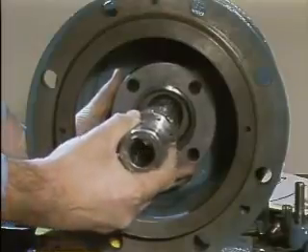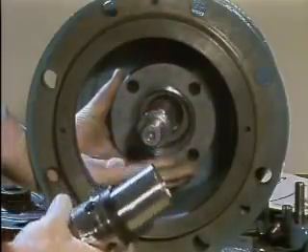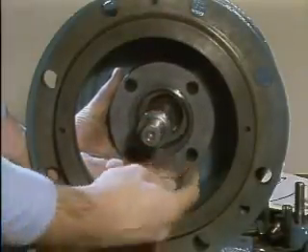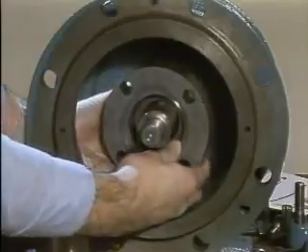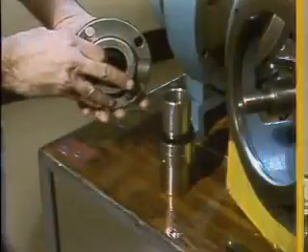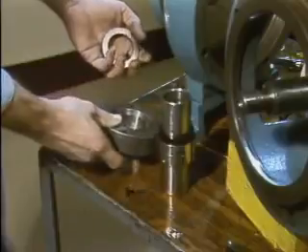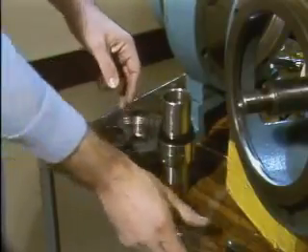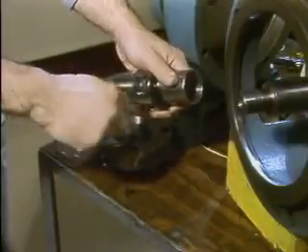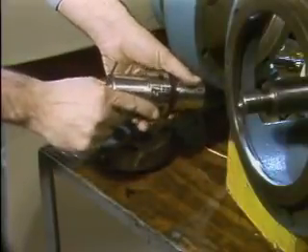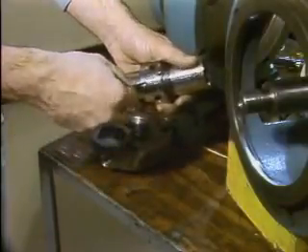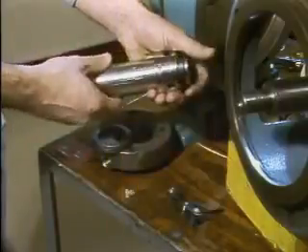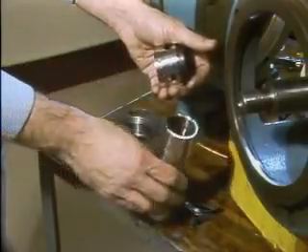Next, the shaft sleeve and the rotating element are slid off of the shaft, along with the gland plate. Then the mating ring is removed from the gland plate by simply pushing it out. After the collar set screws for the rotating element are loosened, the element is slid off of the sleeve.